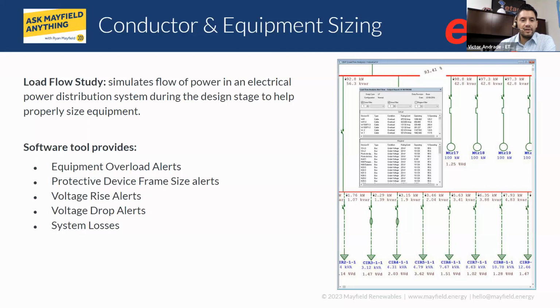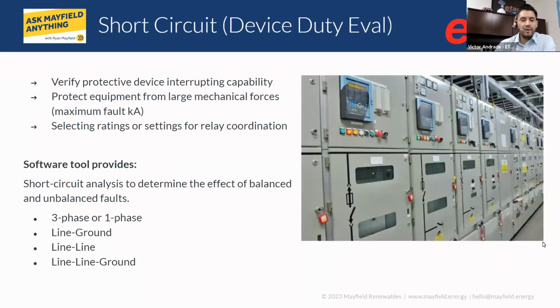Let's go over the next study. For the next study, let's talk about short circuit, and I put device duty evaluation in parentheses because that's the whole purpose of why we do a short circuit study. First of all, it's to protect the equipment. So we perform a short circuit study, not taking into account any protective devices. We simply take the impedance of the system, your cables, transformers, loads, inverters, PV, and we do a fault analysis. And that fault is telling us, in the event of a single line to ground, line to line, or line to line to ground fault, what would be the amount of amps or kiloamps that we can expect at this location. And then we need to compare that against the equipment interrupting rating.